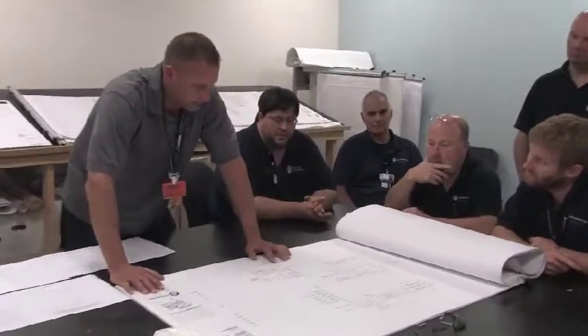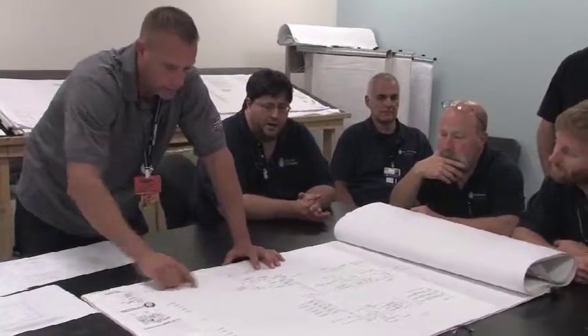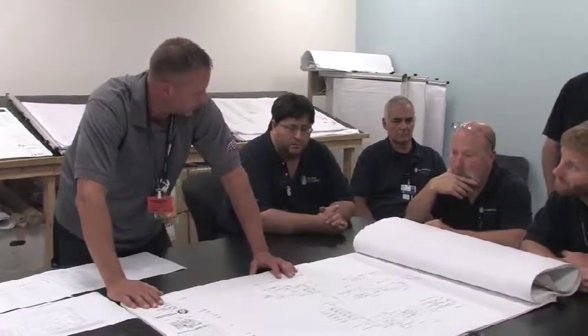And on the 2nd floor, all the returns from the 2nd floor go downstairs to the condensate pump in the tunnel. And there's a heat exchanger in CP1 down there. So they run any water through their heat exchanger on the condensate pump before it goes back to the system, just to pick up any heat before they dump the condensate back to Maytemp. But other than that, it's pretty straightforward.